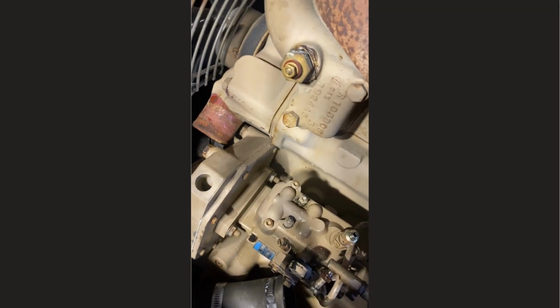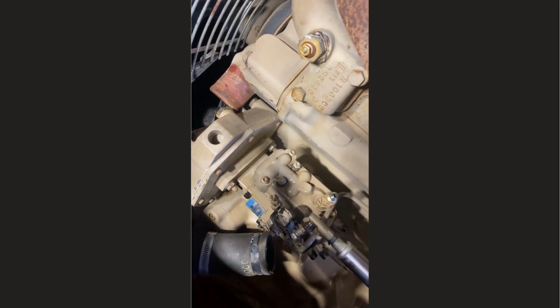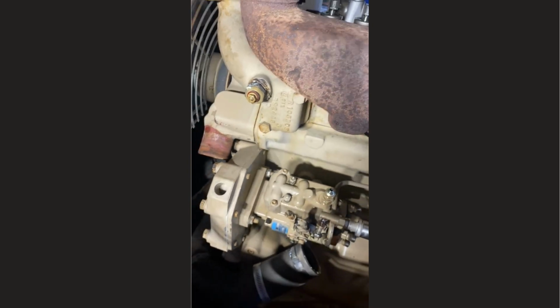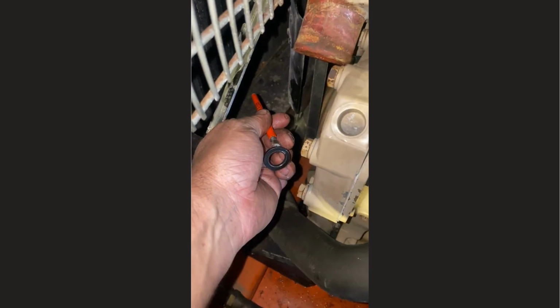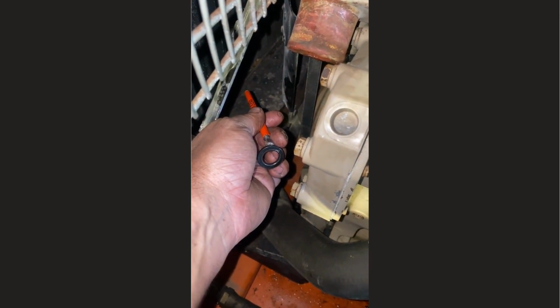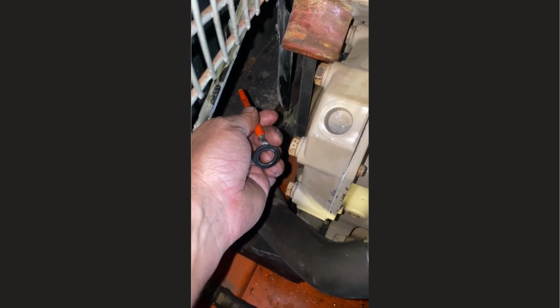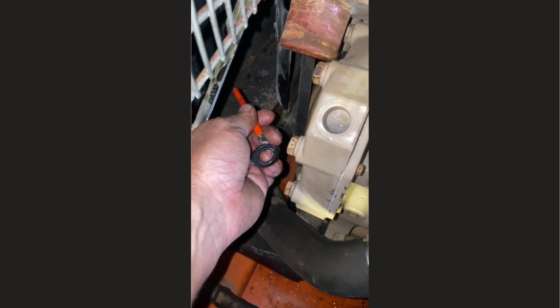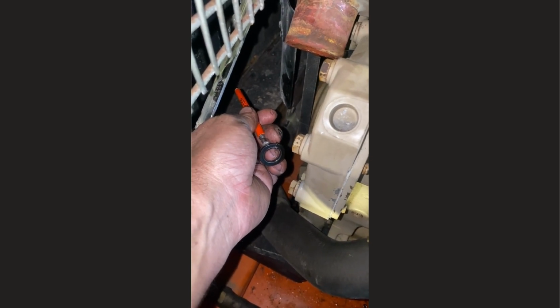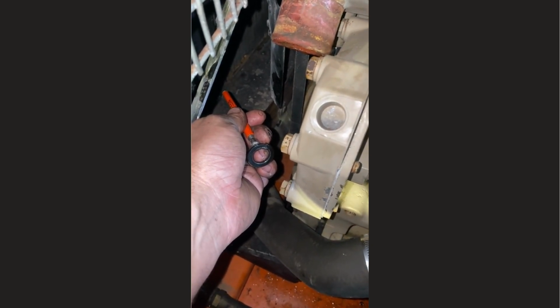Now that we have found top dead center, we now need to access the drive shaft nut access port. We get to pull the drive shaft nut off and use a gear puller to separate the tapered shaft from the drive gear of the motor. Okay, so I removed the access plate and the drive shaft nut. I always pull the lock washer out with a magnet so I don't accidentally drop it down inside the motor.